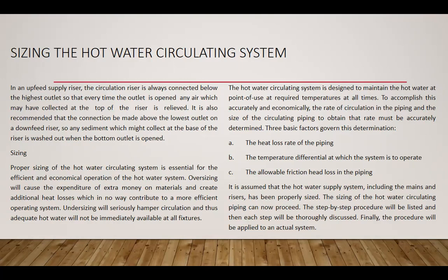Oversizing will cause the expenditure of extra money on material and create additional heat losses which in no way contribute to a more efficient operating system. Undersizing will seriously hamper circulation and thus adequate hot water will not be immediately available at all times.